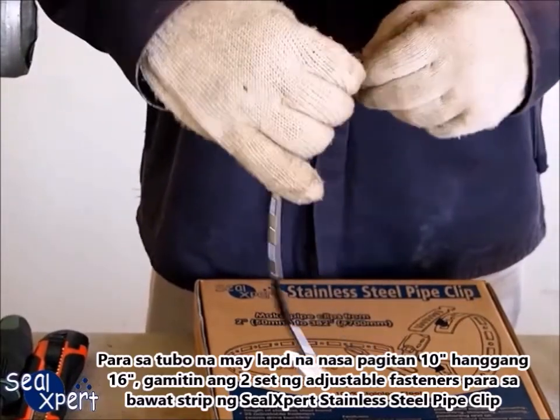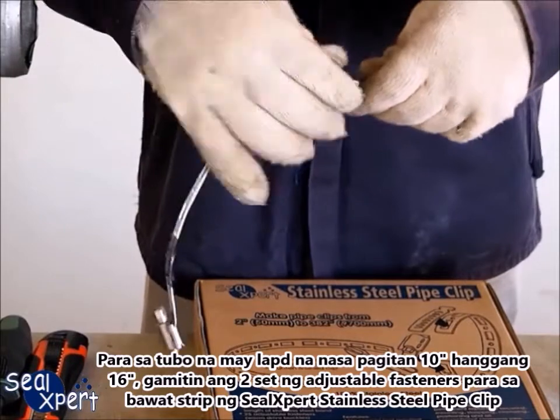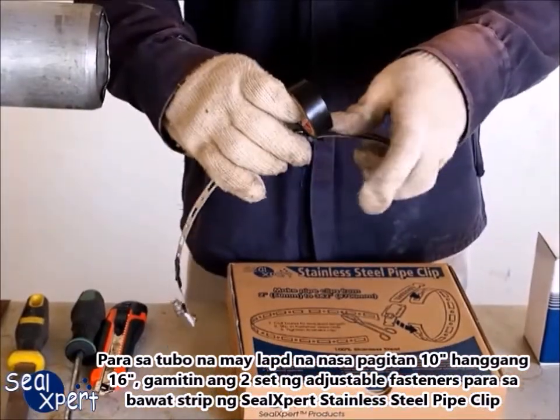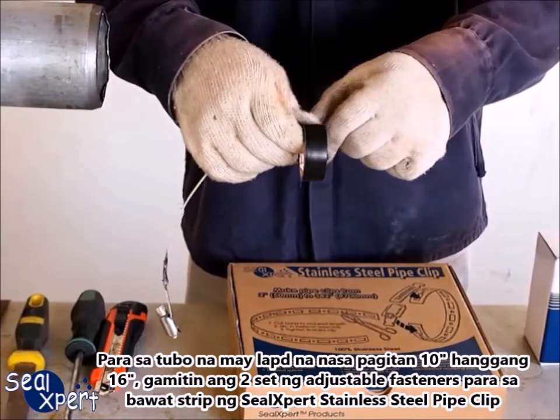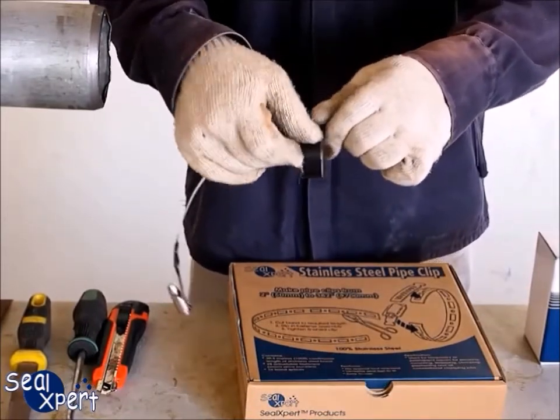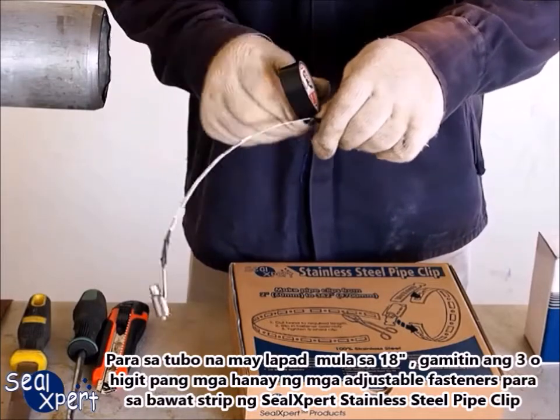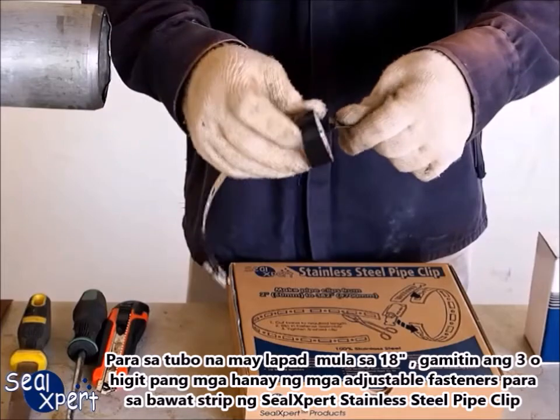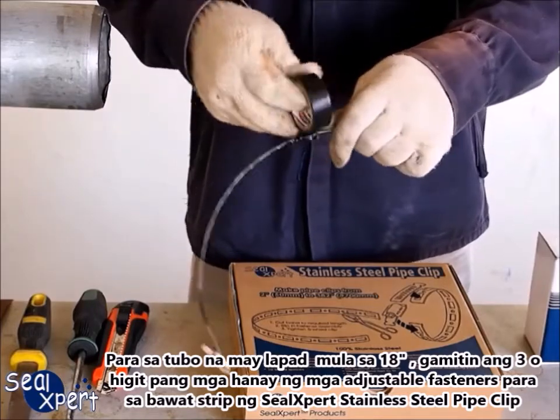For pipe diameter between 10 inches to 16 inches, use 2 sets of adjustable fasteners for each strip of SealXpert STAINLESS STEEL PIPE CLIP. For pipe diameter from 18 inches, use 3 or more sets of adjustable fasteners for each strip of SealXpert STAINLESS STEEL PIPE CLIP.